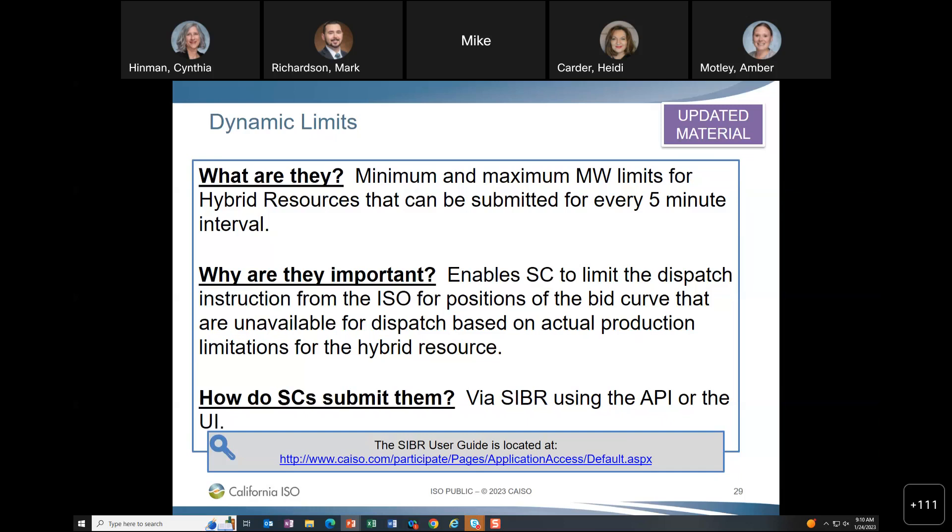If you don't submit dynamic limits, please contact operators to let them know. If not submitted, SIBR will automatically create a dynamic limit using the min and max limits of the energy bid, if one exists. If there's no energy bid but a self-schedule, the dynamic limit will be created using the self-schedule as both min and max. If there is no bid at all, no dynamic limit is needed.